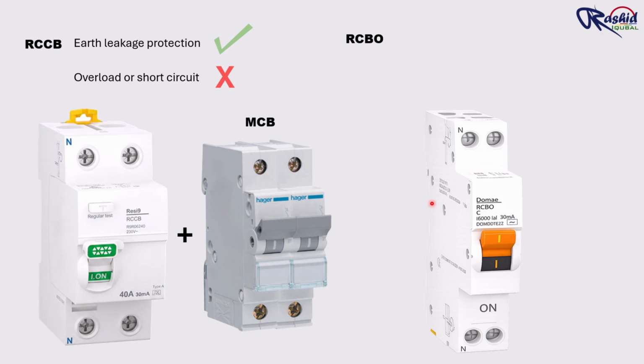This is where the RCBO comes into the picture. Actually, RCBO works on the same principle as a RCCB to detect the earth leakage, but it also has MCB protection built into the same device. This means one RCBO can provide three types of protection: earth leakage protection, overload protection, and short circuit protection.